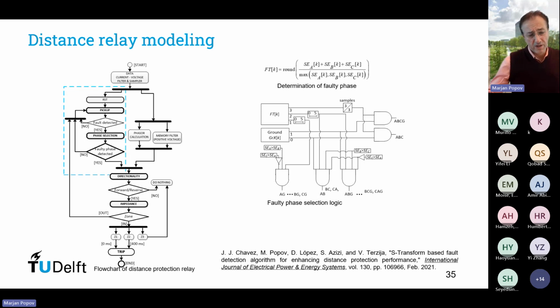Of course, we tested different types of protection, different types of relays. If you search in the publications that we published, there are quite some other results published here. However, the major difficulty in the operation of the protection was actually related to the fault detection. We found that actually the impedance algorithm, well, normally the impedance enters the protection zone of the relay, but the relay does not operate. Therefore, we focused on developing a fault detector in this case.